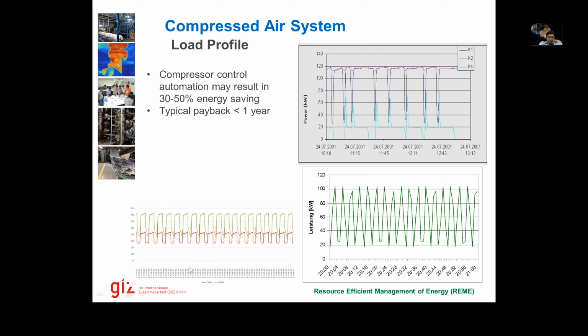Improvement potential here? For this chart, I think it is a waste of energy since two compressors are on load and offload at the same time. So I think that there is a loss on the offload, and that is a waste of energy. They are on load at the same time. So to reduce the energy loss, we will control one to be on full load and one to be on normal load, so they don't conflict with each other.